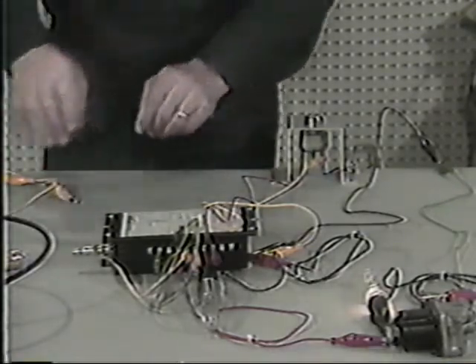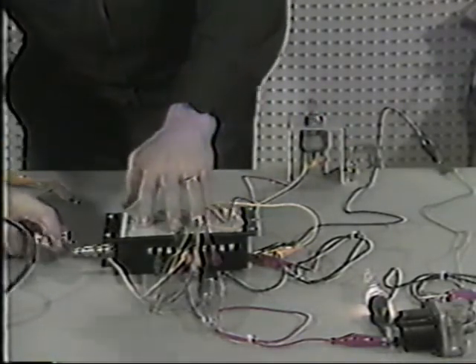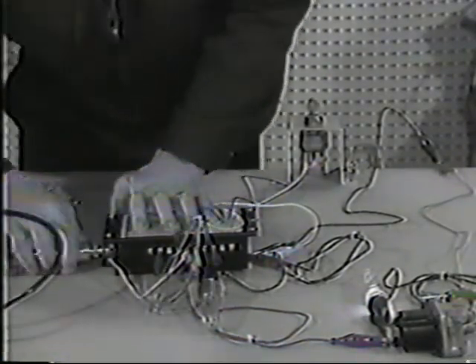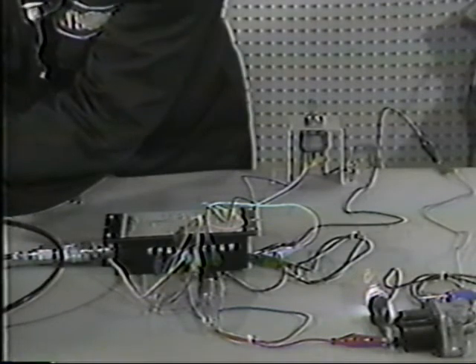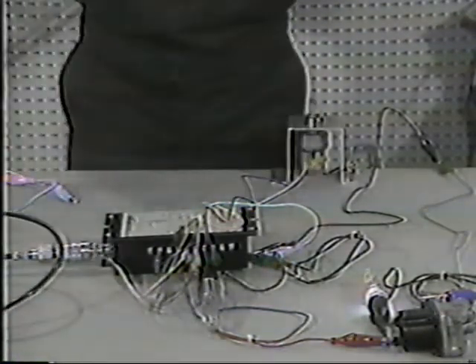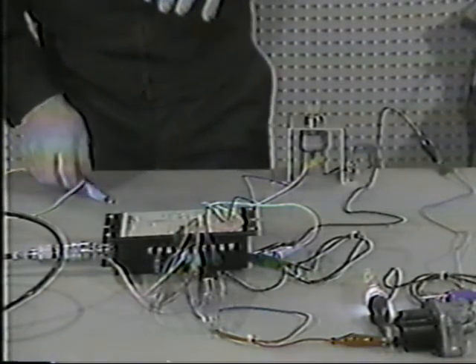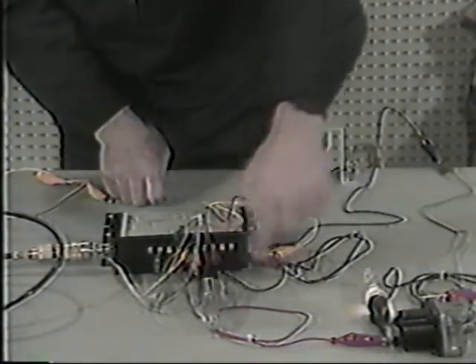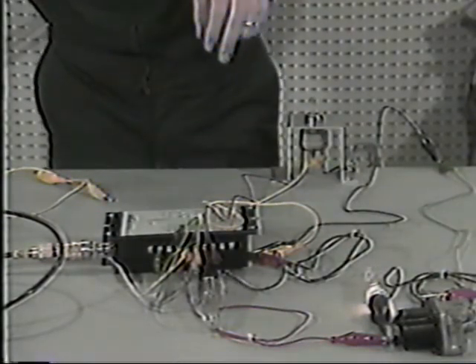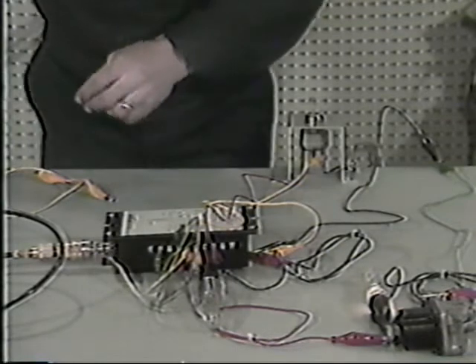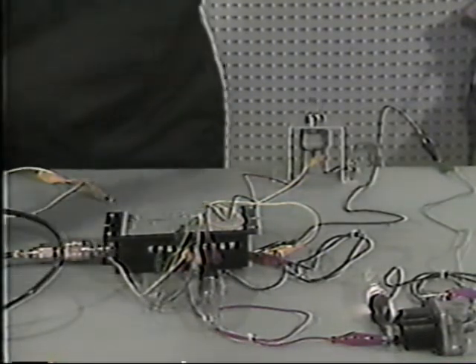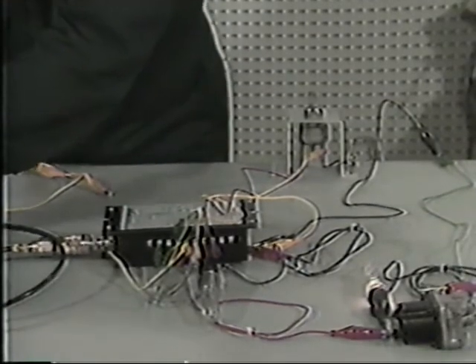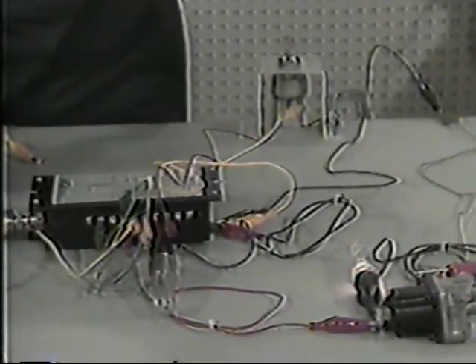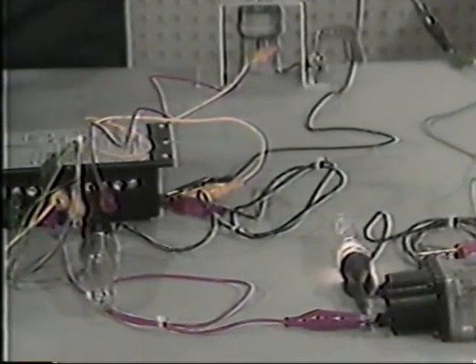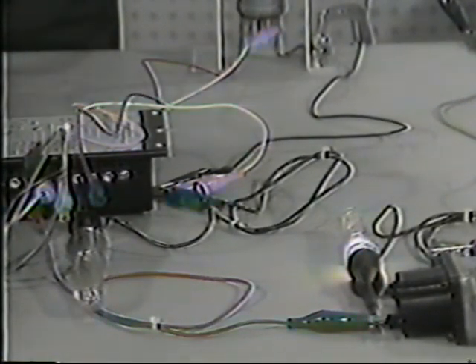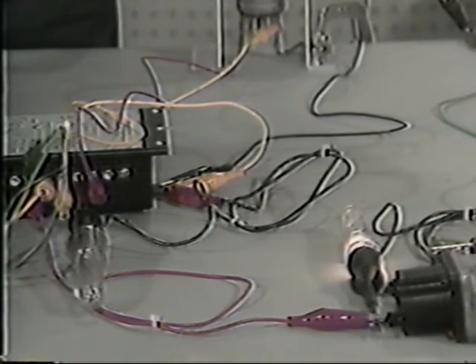Okay. At this point, while the engine is still being simulated as running, go ahead and connect the compressed air supply and bring it up to at least 25 pounds. Okay. With everything connected as you see here, we should have no warning test light, and the fuel solenoid should remain on indefinitely. Now, vent the air pressure down to the point of the alarm setting on the pressure stat. This particular unit has a 20-pound pressure stat, so we should see the warning test light come on as the air pressure vents to that point.